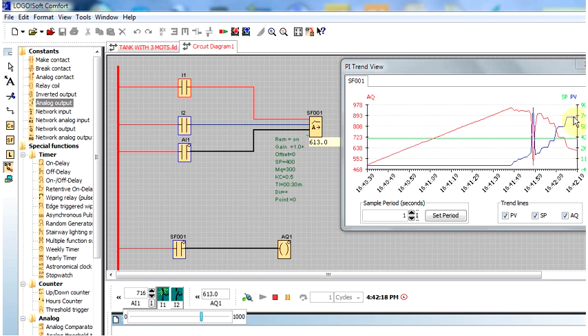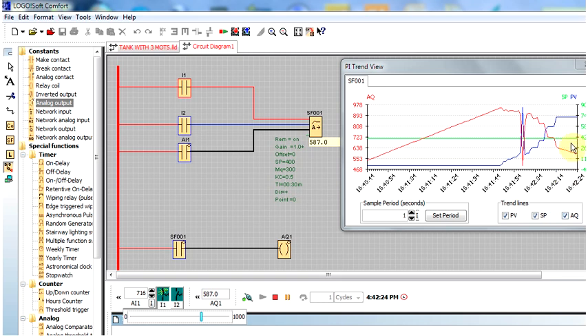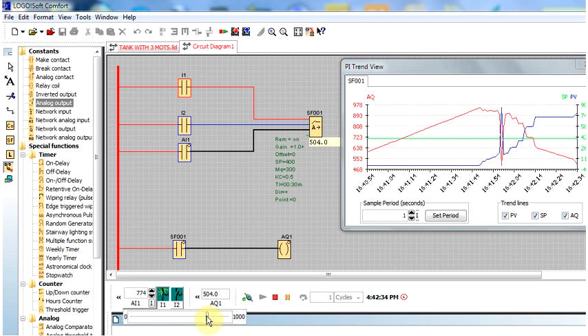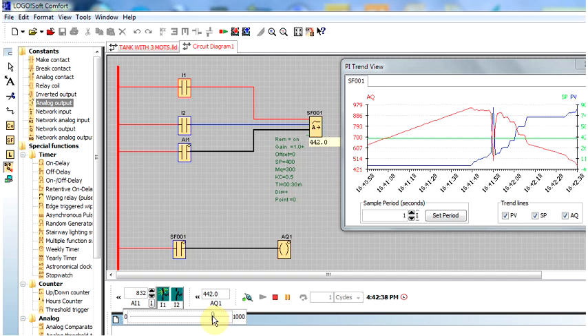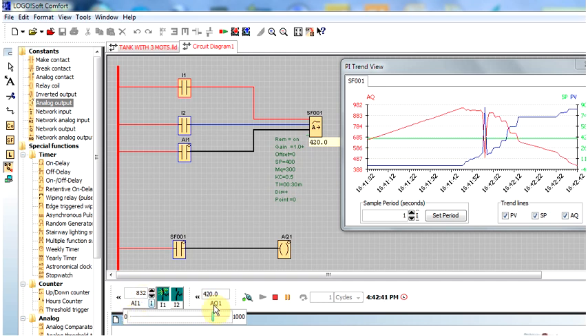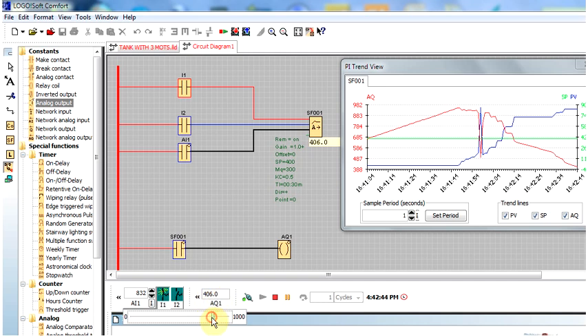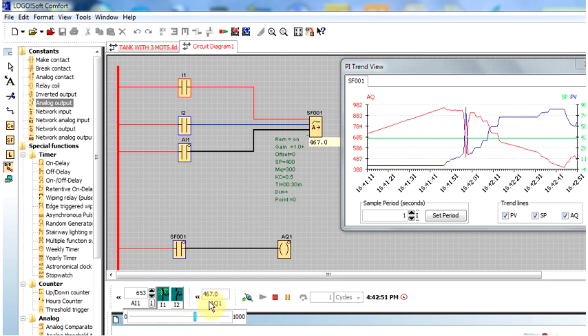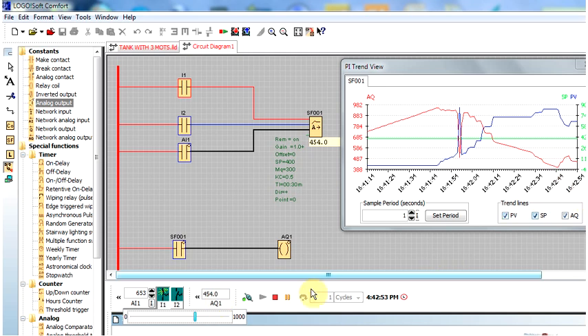Here, the green line is the process value (current tank temperature), and the other line is the set value. The red is the output. From the graph, the more I increase the process value — the tank temperature — the less the flow valve will open. Now the temperature is around 83 degrees centigrade, so about 42% of the valve is open. As I approach 400 degrees, the valve percentage will settle.